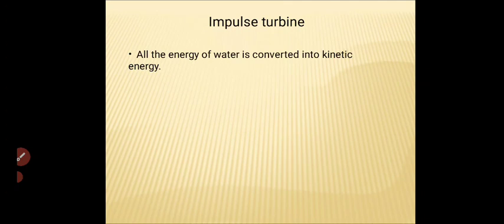Impulse turbine and reaction turbines, hydro turbines are installed to convert the potential energy and kinetic energy of water flow into mechanical work. But the impulse turbine operates based on the change of velocity vectors. In general, the potential energy of water based on the height of waterfall is converted to kinetic energy by one or more nozzles, and then water hits the turbine blades at high speed, causing the turbine to spin and consequently generate electricity.